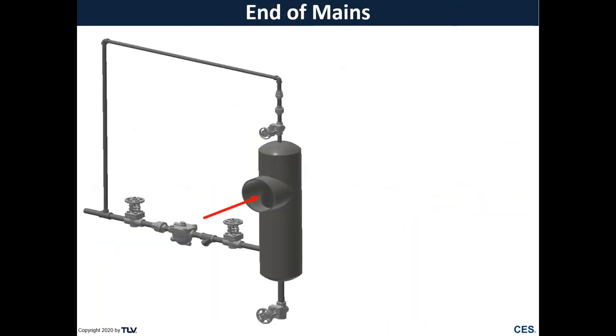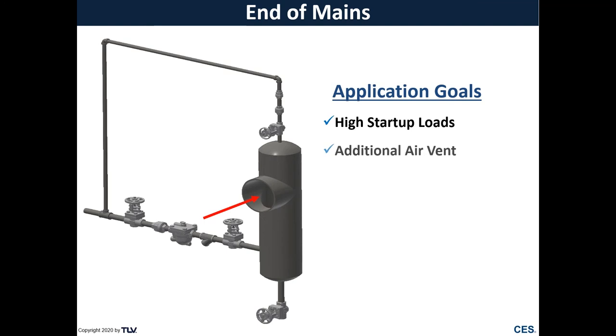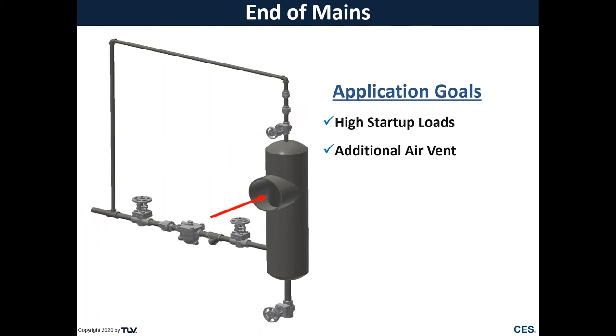Another location is going to be the end of our steam headers, our end of mains. And here we're typically going to see a higher startup load, as well as a high need for air venting, especially on startup, because everything is being pushed to the end of our system.